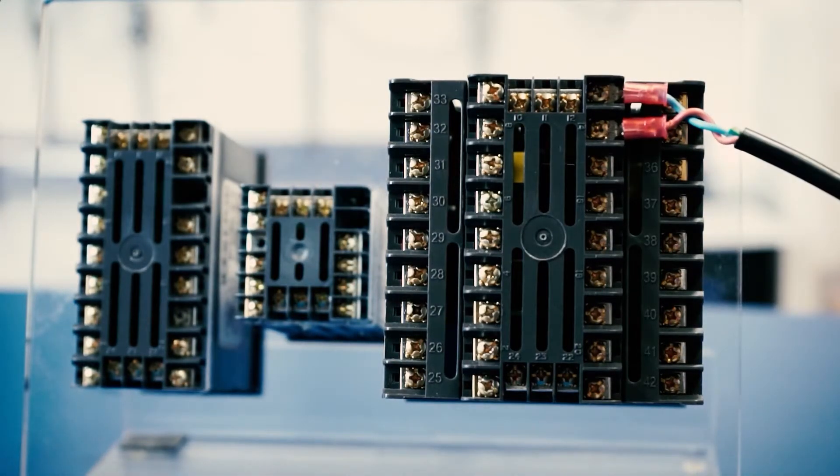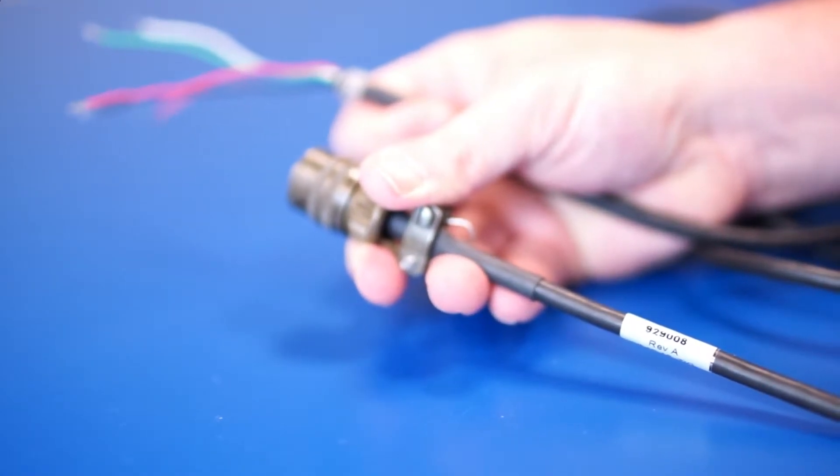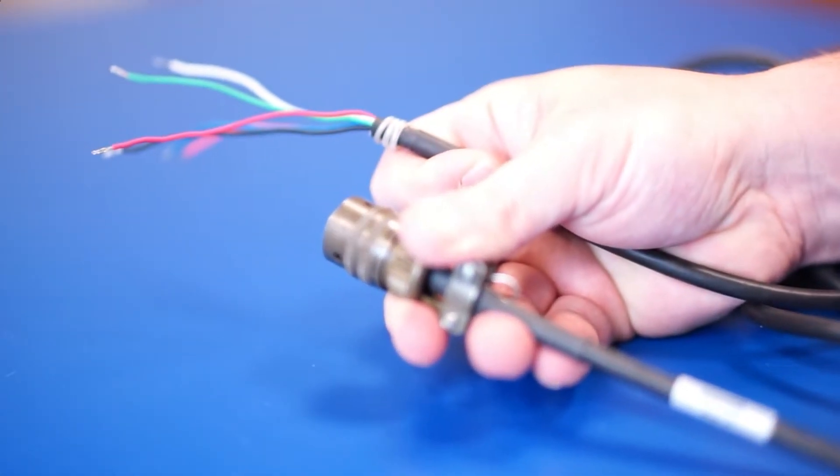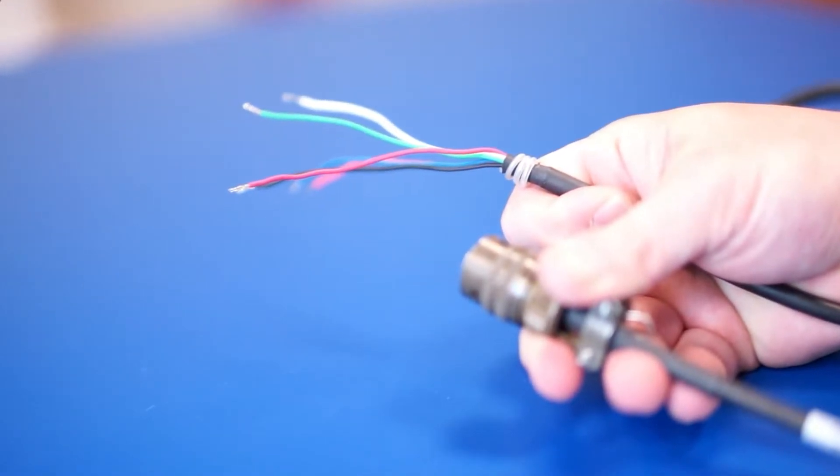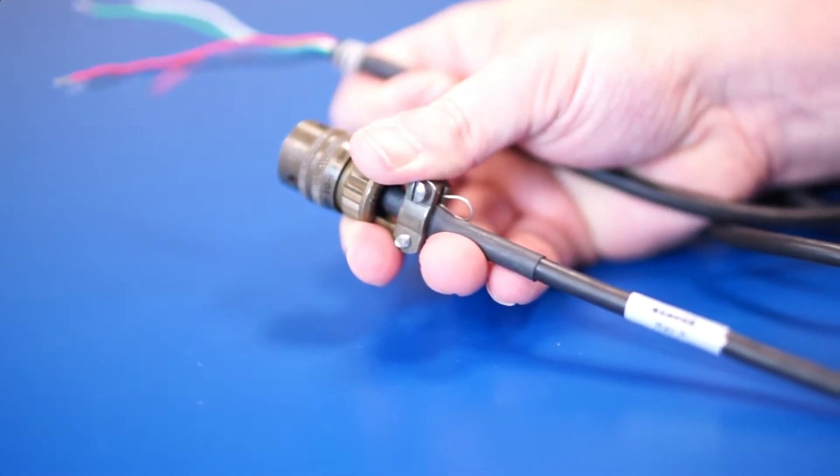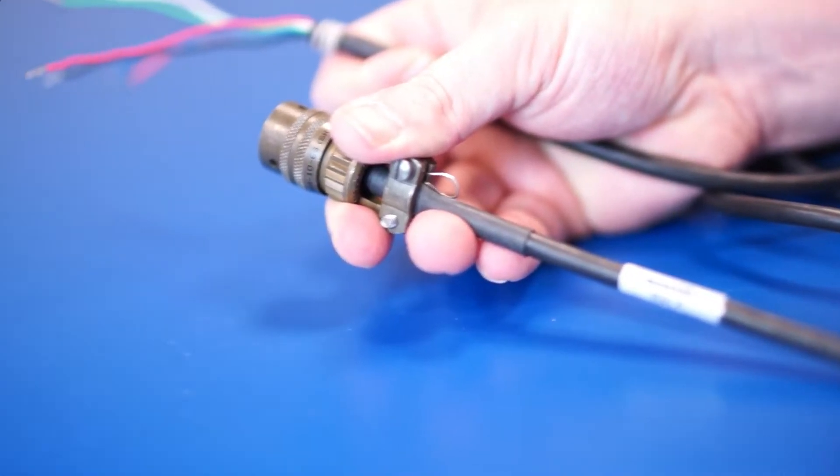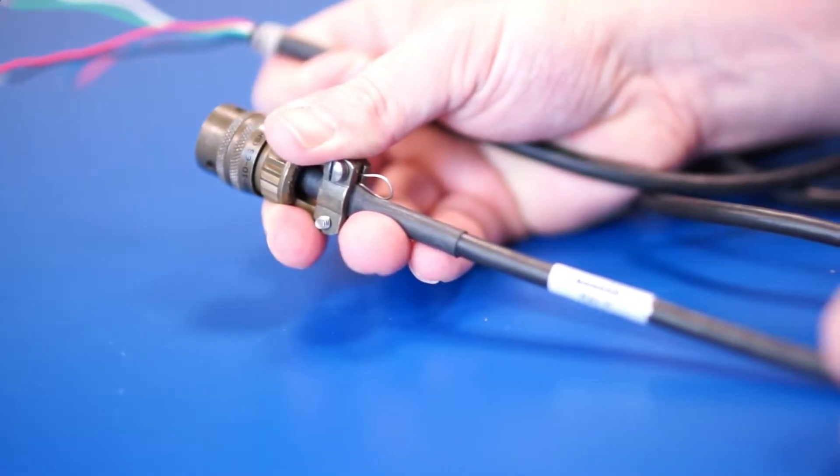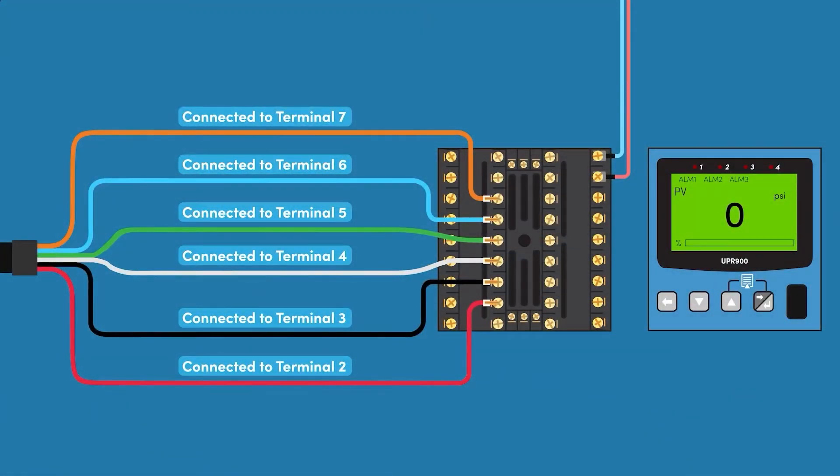With the cable assembly in hand, the bare wires are terminated to the instrument based on the signal output of the pressure sensor. In this example, our pressure sensor has a 0 to 33.3 millivolt output and will utilize all 6 wires. The correct wiring termination is as follows.